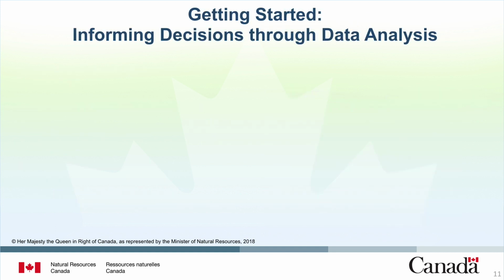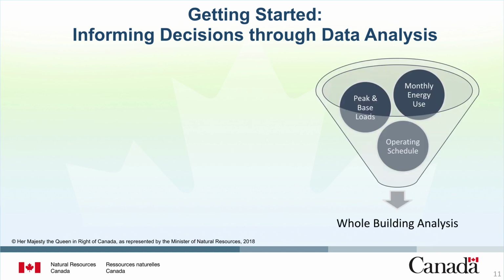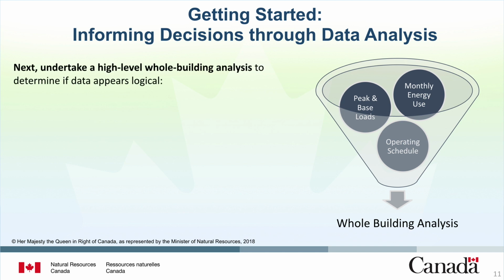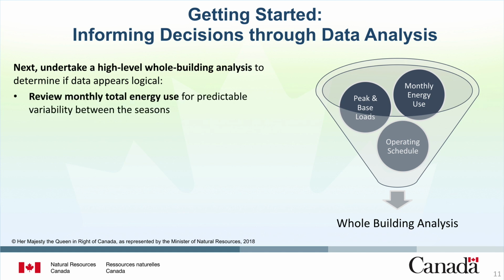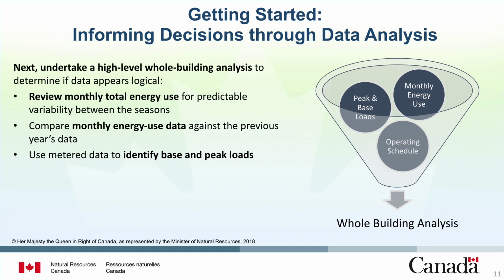Let's outline the steps required to conduct analysis of meter data. Once a building or set of buildings has been selected for analysis, undertake a high-level whole building analysis to determine if data appears logical. To do so, review the monthly total energy use for predictable variability between the seasons, such as higher energy use in the summer months to support air conditioning. Compare monthly energy use data against the previous year's data for variability or similarities. Next, use the meter data to identify base and peak loads. Finally, review the operating schedule to confirm building systems are operating as intended.